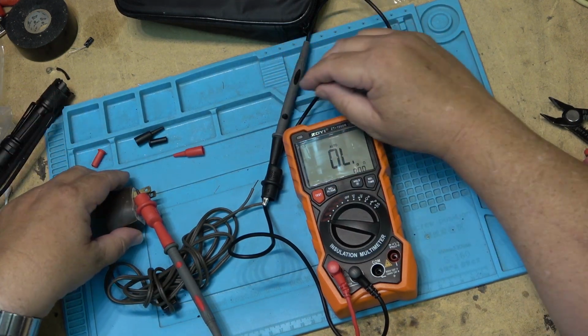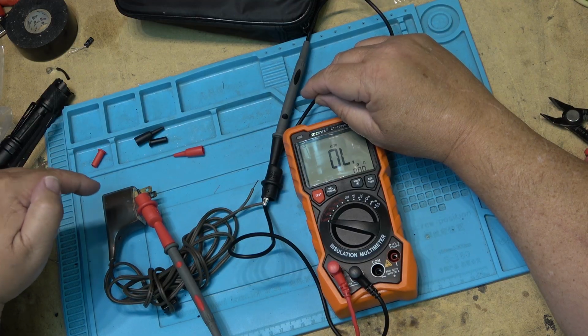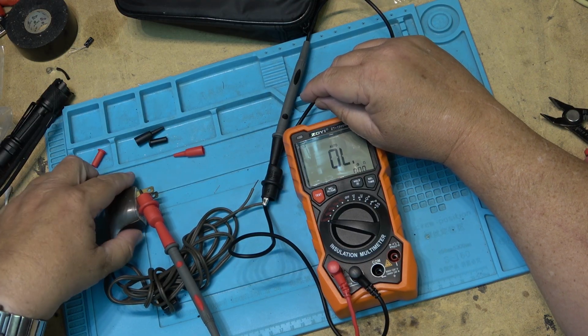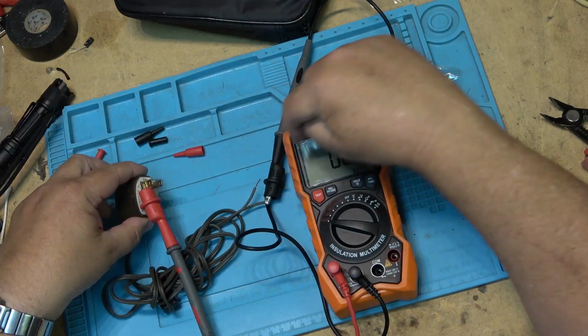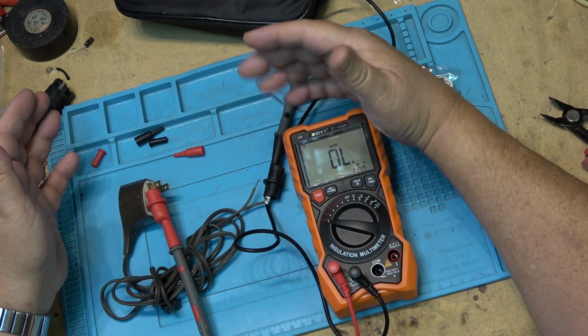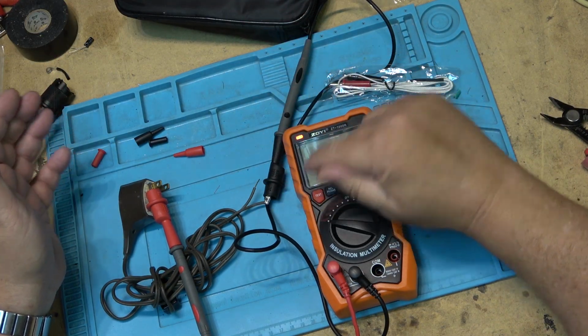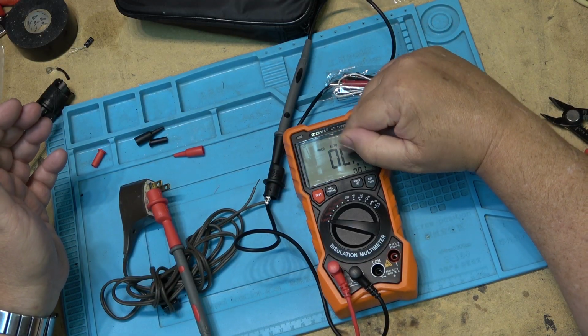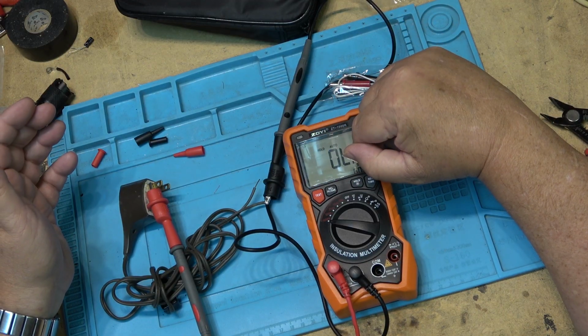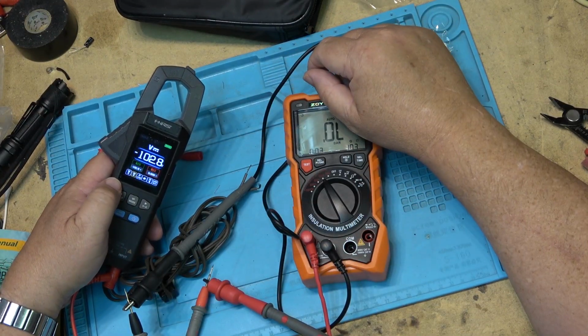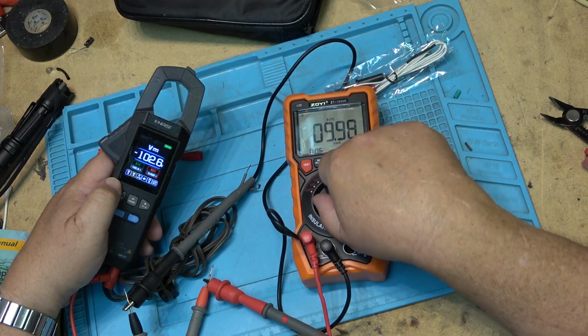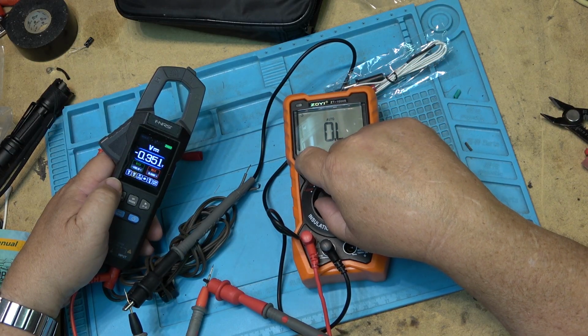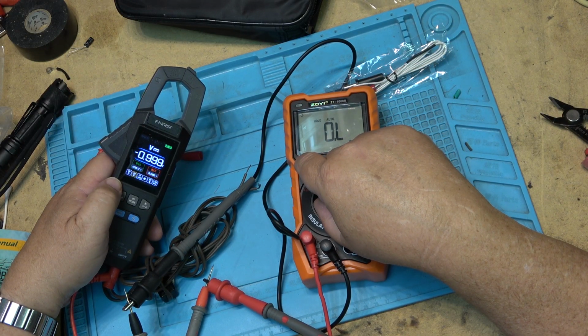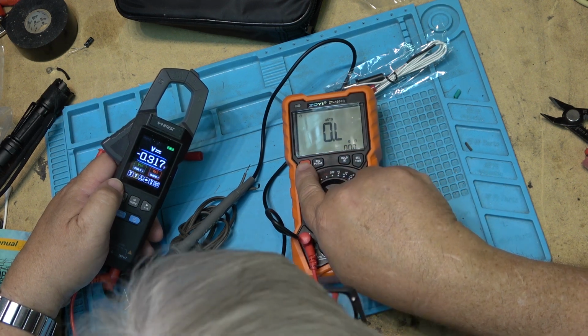So what I'm going to do now is provide a 1,000 volt pulse between, this is just a regular magnetic transformer, one side's on the primary, the other side's on the secondary. If there's any breakdown in the insulation, it will show up as a fault. But because there is no breakdown in the insulation, it's showing overload. It's generating 1,000 volts. So this will keep the voltage on. I'm going to do that.